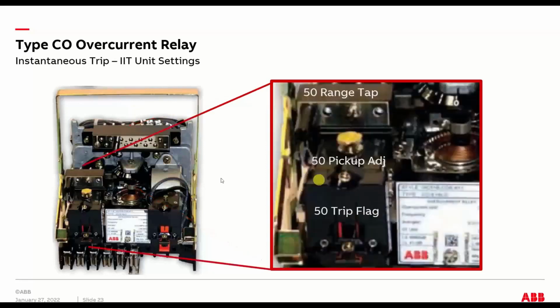You spin it until it meets the setting. That's it. This relay also has instantaneous, or 50, protection on it, and that's just a separate element contained in the relay right here. Its settings are really simple too. You have a range tap, which is the same as the other tap. It's a screw that screws into whatever hole you pick. And then there's a pickup adjustment dial. That's all there is to it. And this piece here would be a flag that drops if it picked up on that. But the point I'm getting across is that for an electromechanical overcurrent relay, you had the 51 tap, the 51 time dial, and then the 50 pickup with maybe a range. Sometimes there weren't even ranges on them, depending on the model.